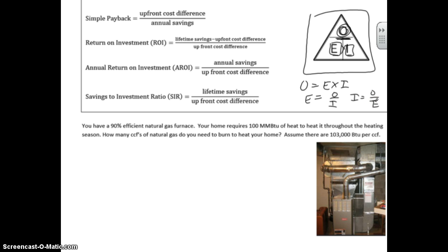Let's use those equations and figure out our problem. In this case, we have a 90% efficient natural gas furnace. We need 100 mmBTUs to heat the home, and we want to know how many CCFs of gas do we need to heat the home. We will assume there are 103,000 BTUs per CCF.